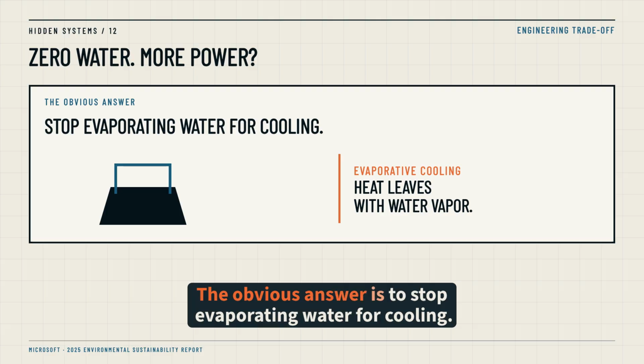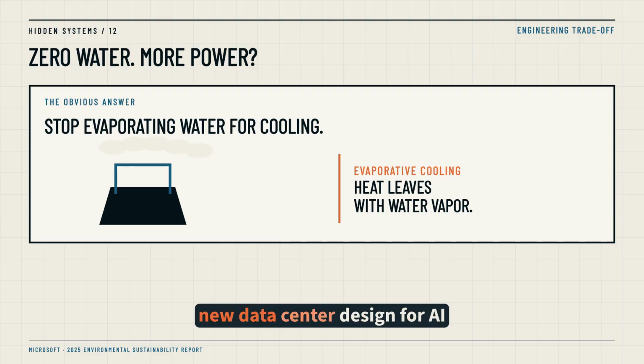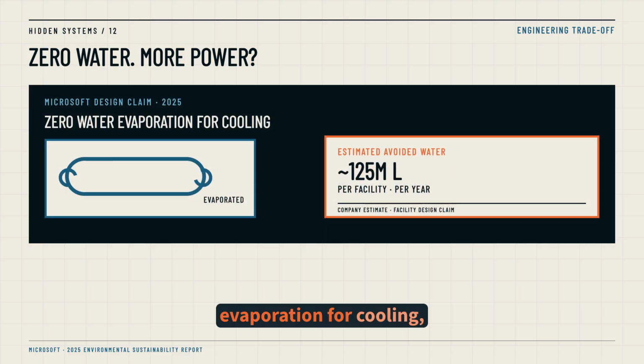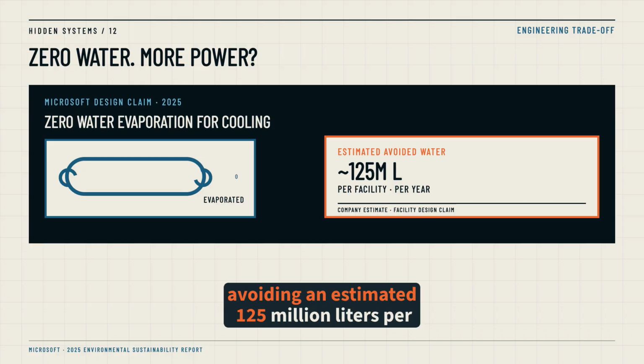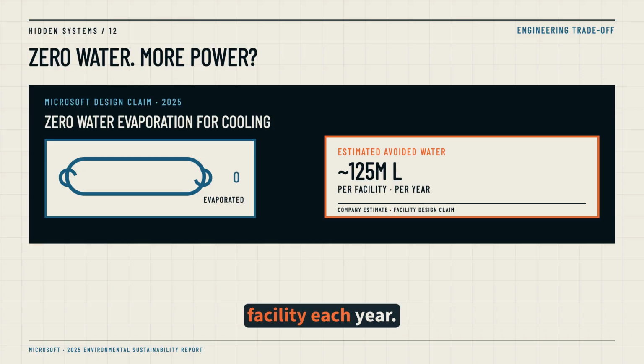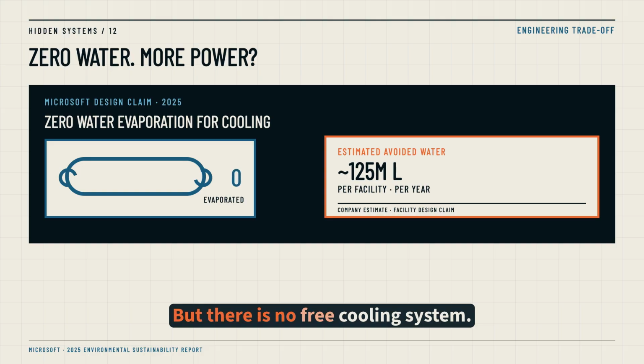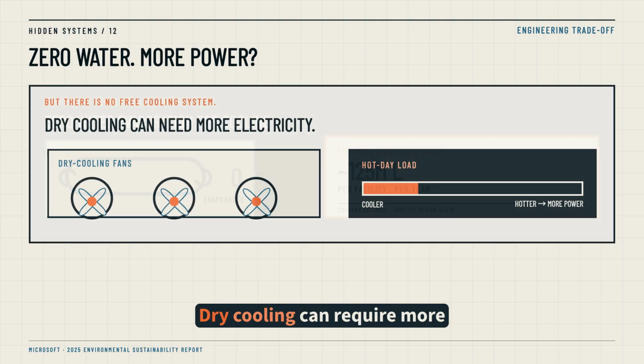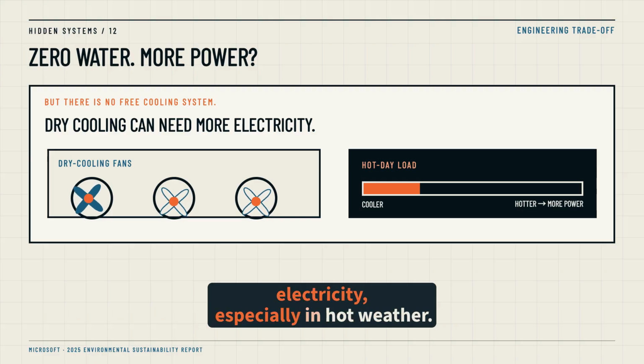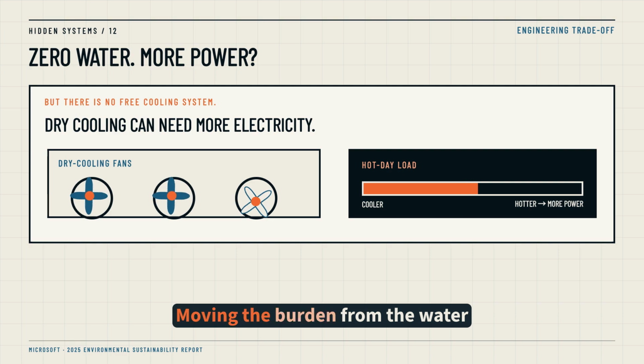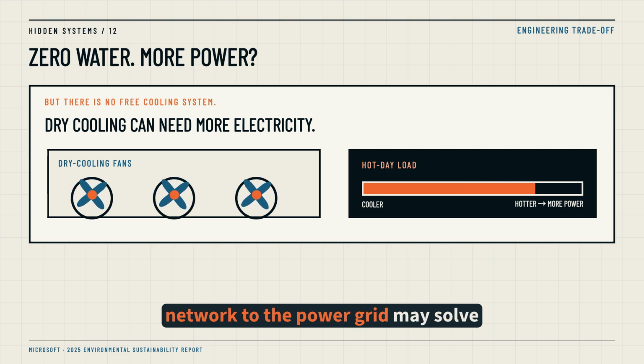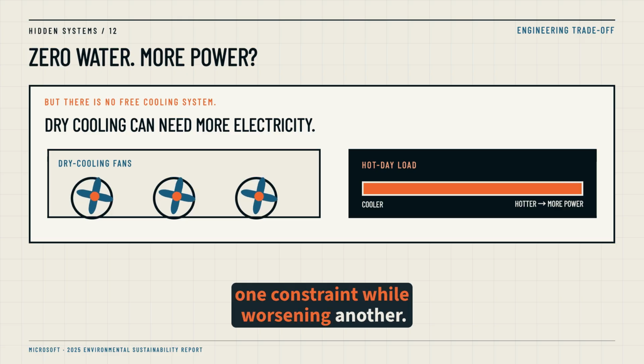The obvious answer is to stop evaporating water for cooling. Microsoft says a new data center design for AI workloads can operate with zero water evaporation for cooling, avoiding an estimated 125 million liters per facility each year. But there is no free cooling system. Dry cooling can require more electricity, especially in hot weather. Moving the burden from the water network to the power grid may solve one constraint while worsening another.